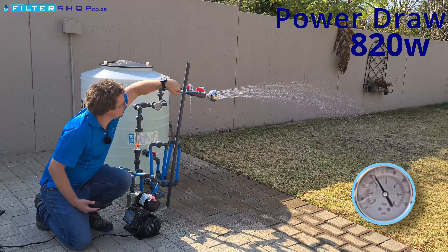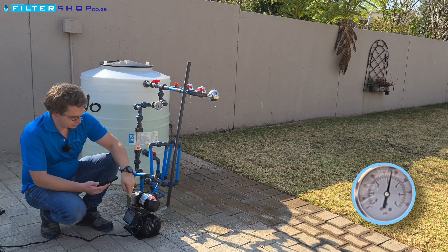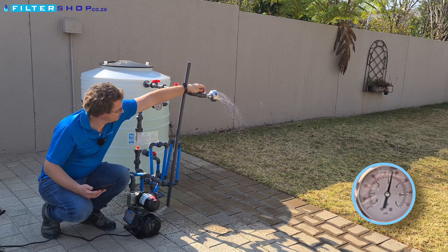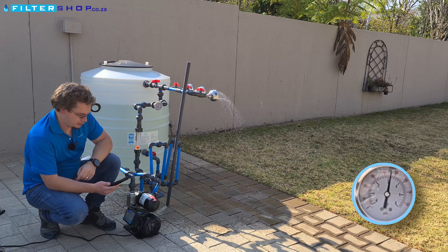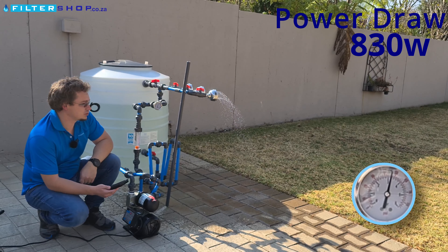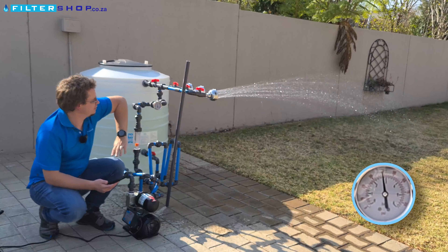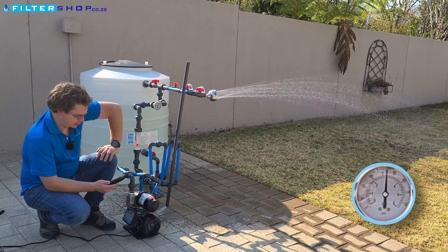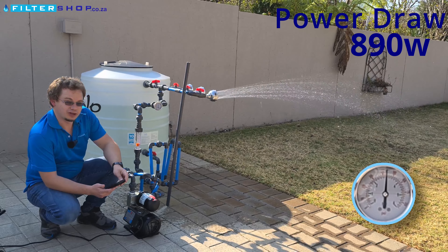Still at maximum power consumption. Let's see out of interest how it does if we set it to three bar. With just a small load we're getting to the three bar target, but we're drawing 820 watts for just a small flow at three bar. At that point you're not really gaining anything from the variable speed drive pump if you're at three bar or higher. For a single shower we're managing to keep 2.8 bar on its gauge, almost at three bar, but drawing 890 watts.